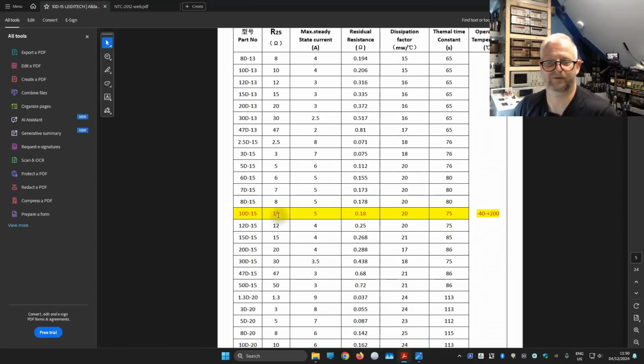So if we take this one, it's rated for a steady current of 5 amps. We have 240 volts here, so times 5 amps is above 1200, so we're good here with 5 amps. When it's warm, we have less than an ohm, so it's basically not there anymore. Of course, I might pick something a bit heavier, maybe a 10D20 or similar.